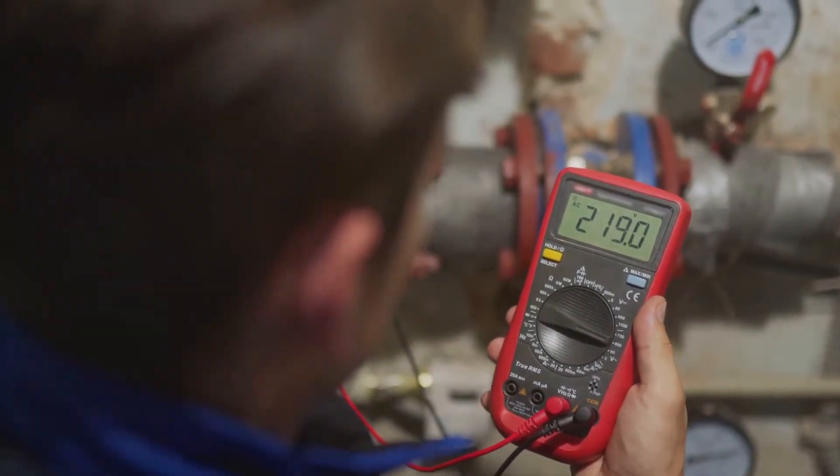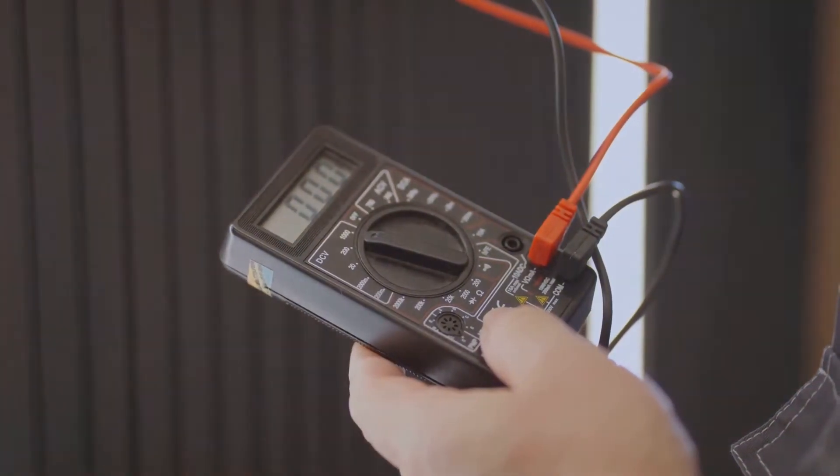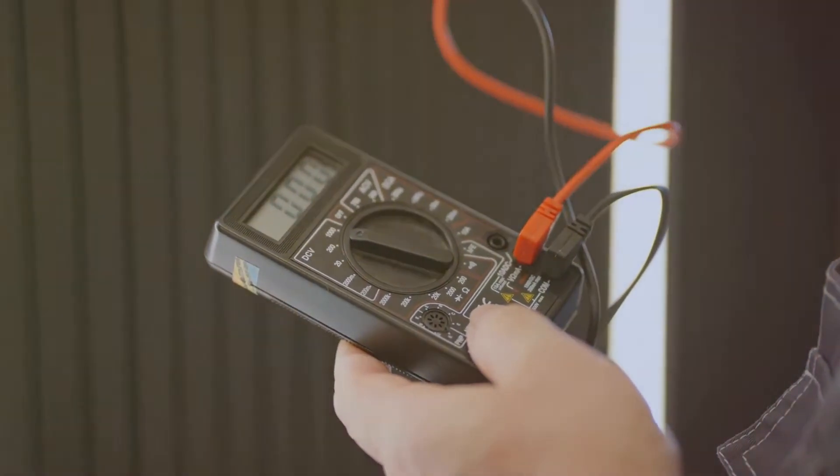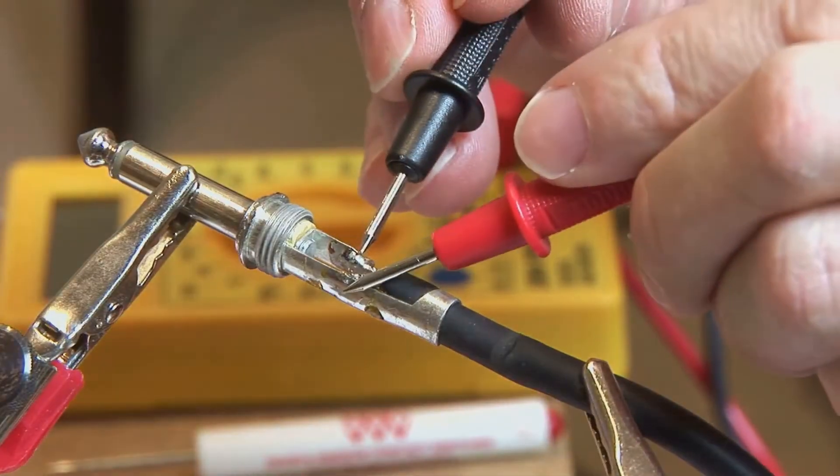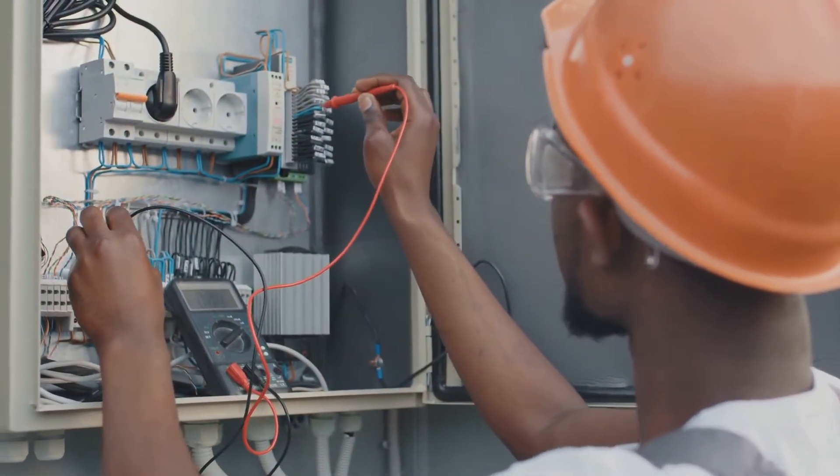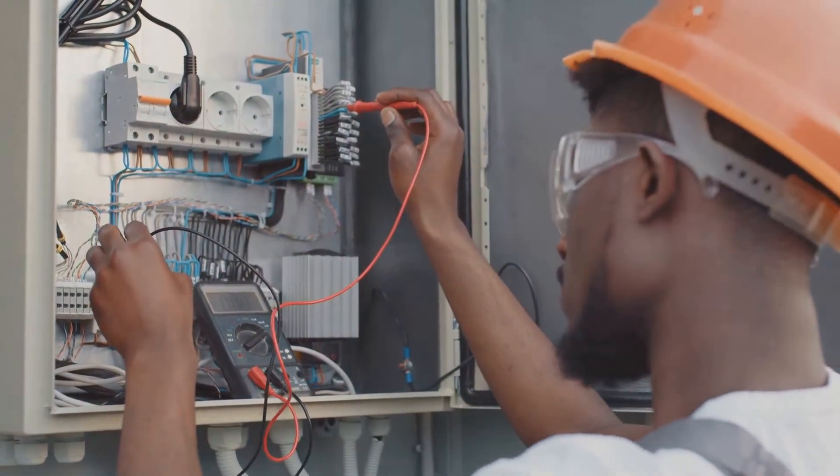If the multimeter reads infinity or OL (open loop), it means there's no electrical continuity through the coil. This indicates a break in the wire somewhere. A solenoid with a broken coil is as useful as a screen door on a submarine.